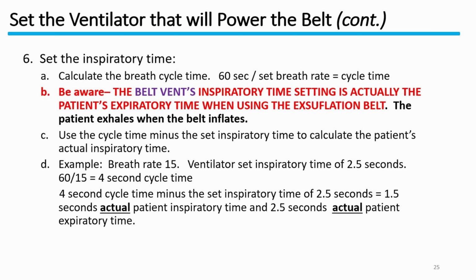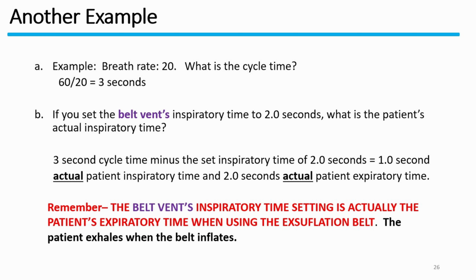Breath rate 20. What is the cycle time? 60 divided by 20 is 3 seconds. If you set the belt vent's inspiratory time to 2 seconds, what is the patient's actual inspiratory time? A 3-second cycle time minus the set inspiratory time of 2 seconds equals a 1-second actual patient inspiratory time and 2 seconds actual patient expiratory time. Remember, the belt vent's inspiratory time setting is actually the patient's expiratory time when using the exsufflation belt. The patient exhales when the belt inflates.